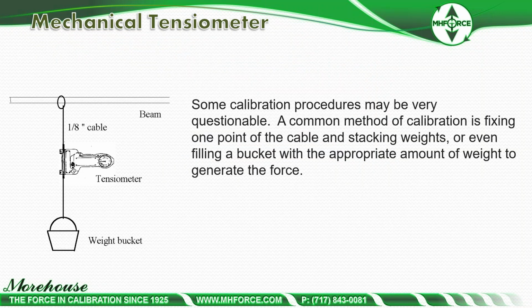And here's fun stuff. You look on Google, and Google tells you, hey, you can calibrate a tensiometer this way. Some calibration procedures may be very questionable. Yeah, weight bucket's a questionable one. A common method of calibrating is fixing one point of the cable and stacking weights, or even filling a bucket with the appropriate amount of weight to generate the force. I saw this, people using it, that's fine. As funny as it may be, if you know your force values, you know the weight of the bucket, you know everything else, maybe this is an acceptable method.